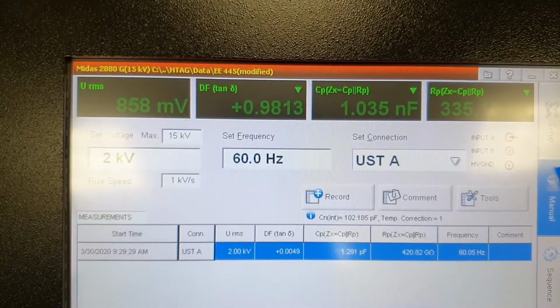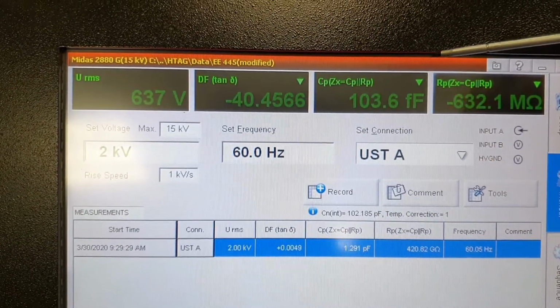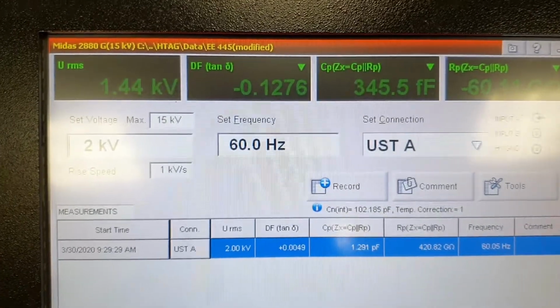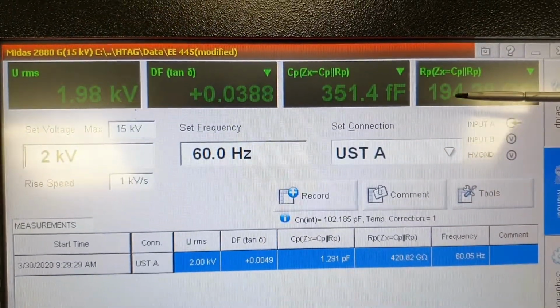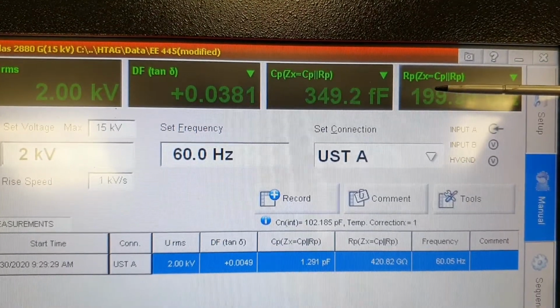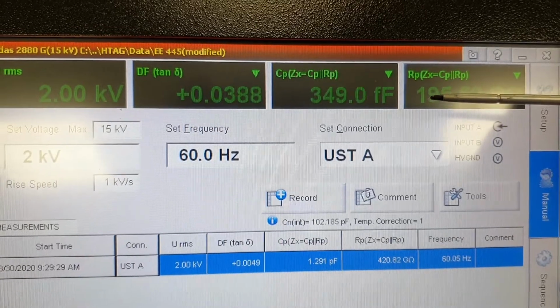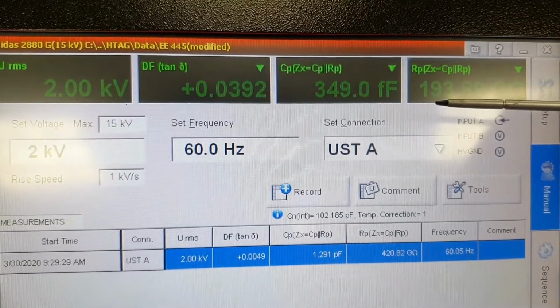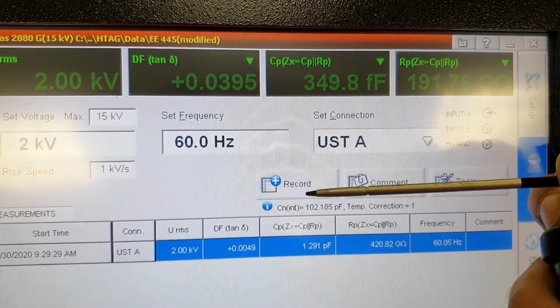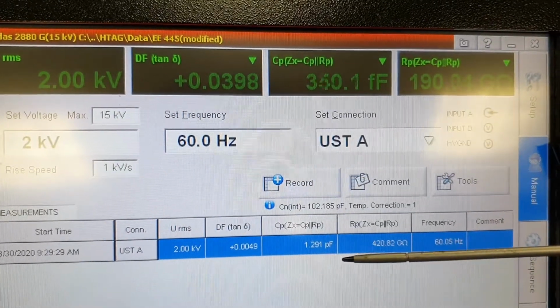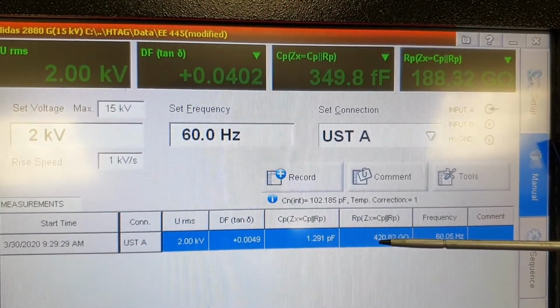So it will try to calibrate again and it is trying to measure. Once this bar is red here, that means high voltage is on. You'll see these are still very dim numbers. Once they become very bright green ones, that means the values have stabilized and you can record that time. So you'll just press this record button to record those values in the second line here.